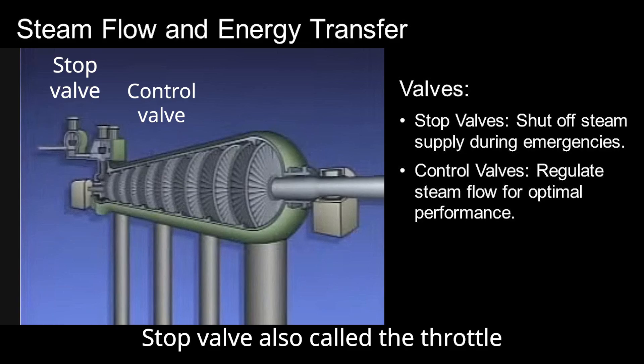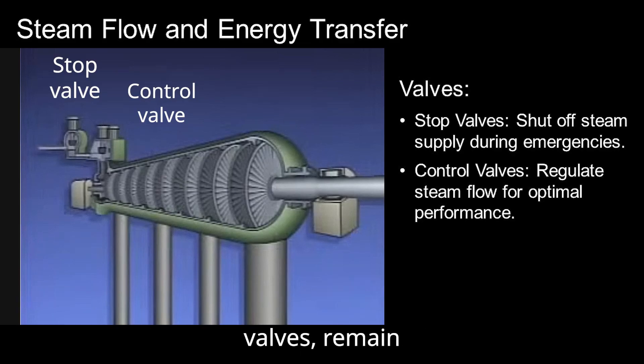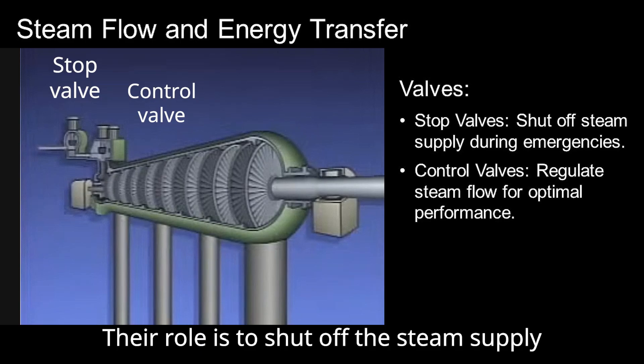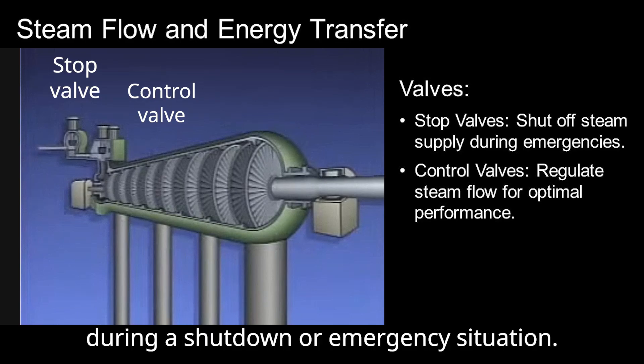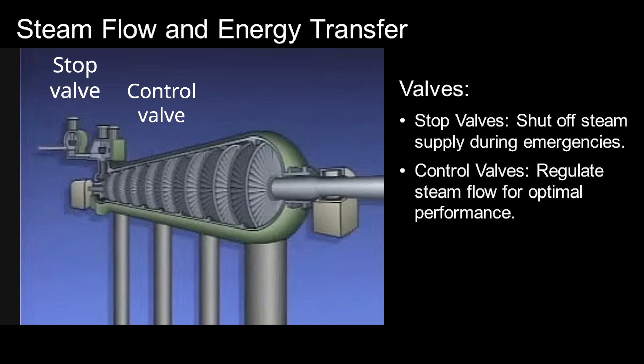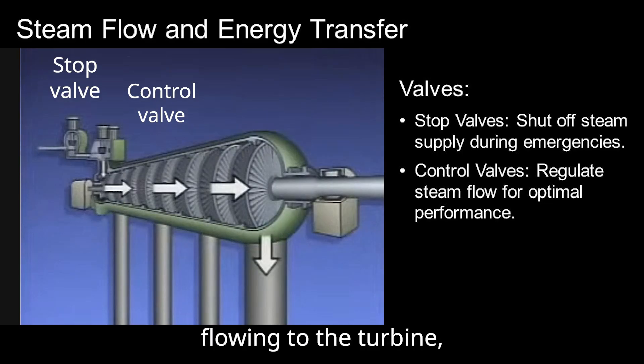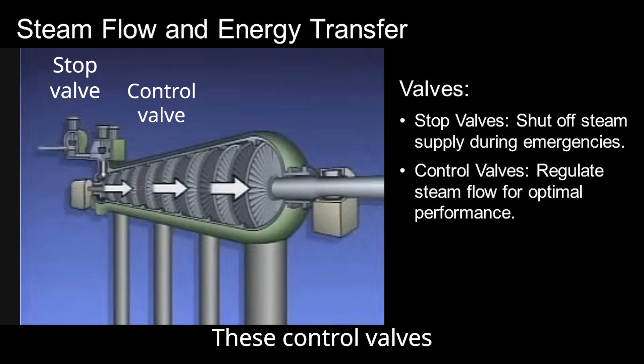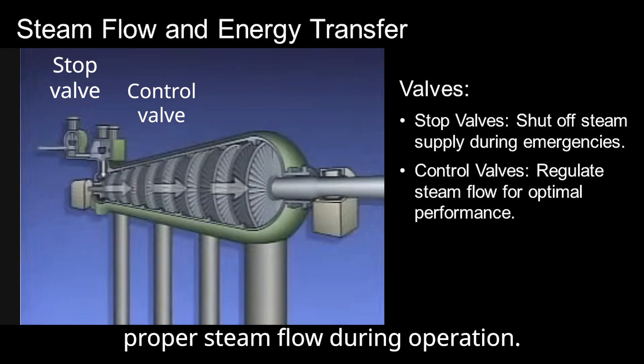Stop valves, also called throttle valves, remain fully open during normal operation. Their role is to shut off the steam supply during a shutdown or emergency situation. Control valves regulate the amount of steam flowing to the turbine, adjusting for optimal performance. These control valves help maintain proper steam flow during operation.